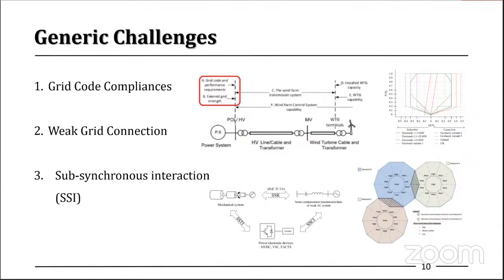The CIGRE technical brochure 671 on connection of wind farms to weak AC networks defines weaker grids. Basically, if the short circuit ratio is between 3 to 5, it's defined as a weak grid, or if it is less than 3, it's defined as a very weak grid.